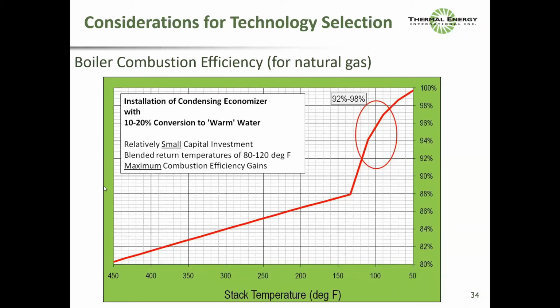So Robert, what about in a building where you need that 180 in, under peak design conditions, but then you have a reset and you're going all the way down to 120 depending on your outdoor air temperature? Would you have a combination of non-condensing and condensing so that you can use the condensing boiler when it's milder temperatures outside, and then still attach your separate condensing unit to the non-condensing boiler? Or how would you do that?